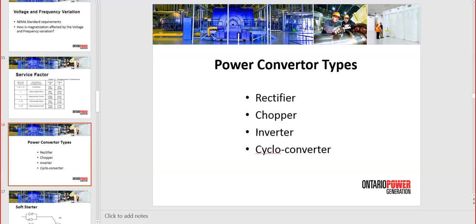streetcars. So inverters are doing the reverse job of a rectifier. It's taking a DC input and converting it to an AC output. But by doing that, through the pulse width modulation process, reconstructing the sine waves, the inverter also creates harmonics, because anything that is non-linear, like a magnetic core, capacitor, or saturated core, gives third harmonic. Chopping a certain wave with switching IGBTs, insulated gate bipolar transistors, in the inverter will also create harmonics. Now the total of the harmonics is called total harmonic distortion, and that's what heats up the motor.